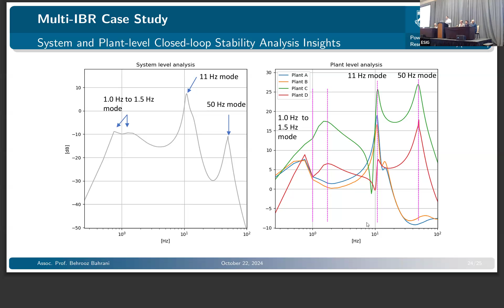There is also a very important feature that we are hoping to add in the near future. It is operating point dependency: understanding how we can make sure that with a limited number of scans, we can have all the operating points available to us, with some sort of extrapolation, so that we don't need to repeat scans for every single operating point. Because at the end of the day, scanning is the most time-consuming part of the tool. It takes time depending on the frequencies you're interested in, what the minimum frequency is, and how many of those frequencies you're interested in. That will determine how long your scan will take.